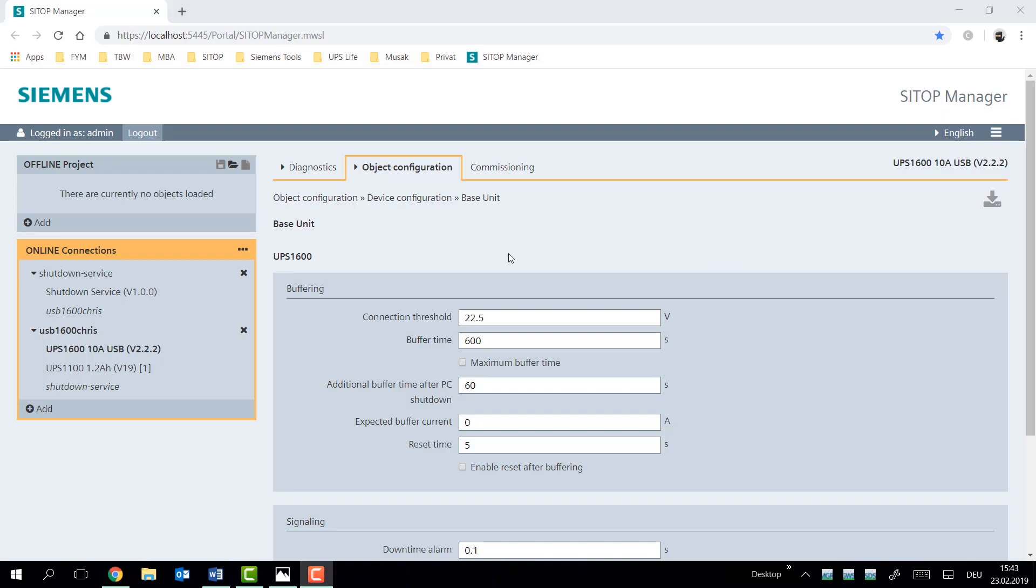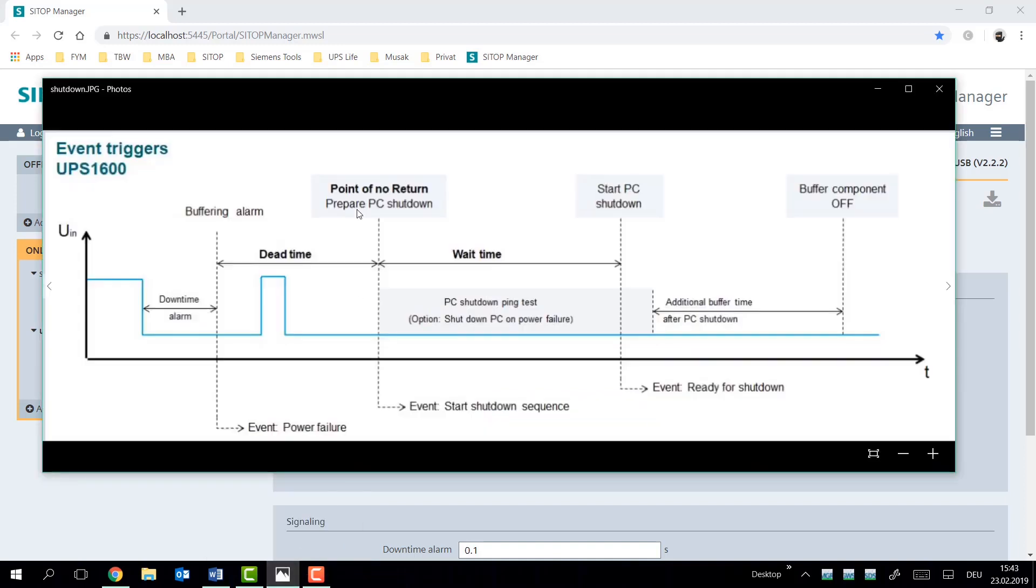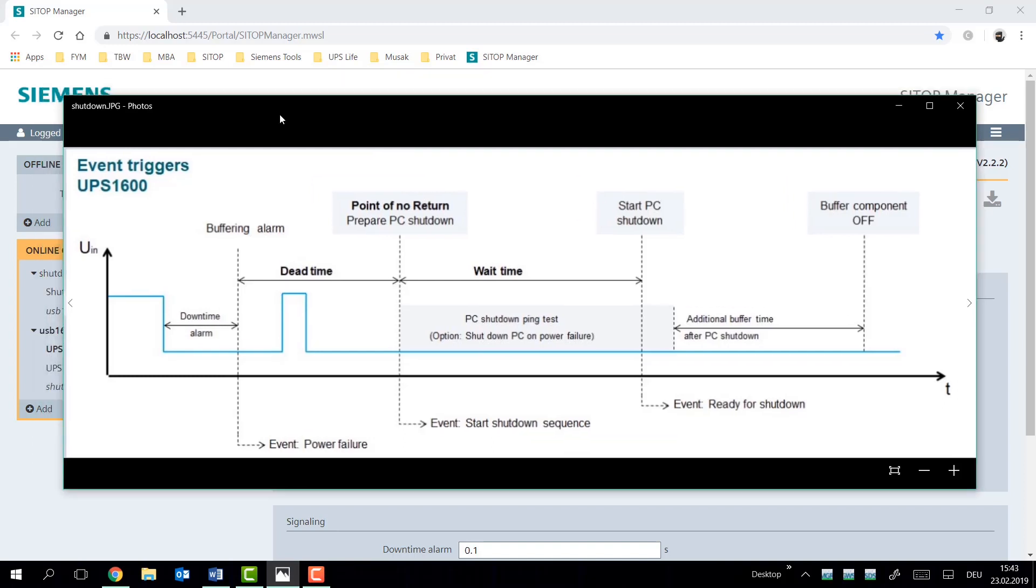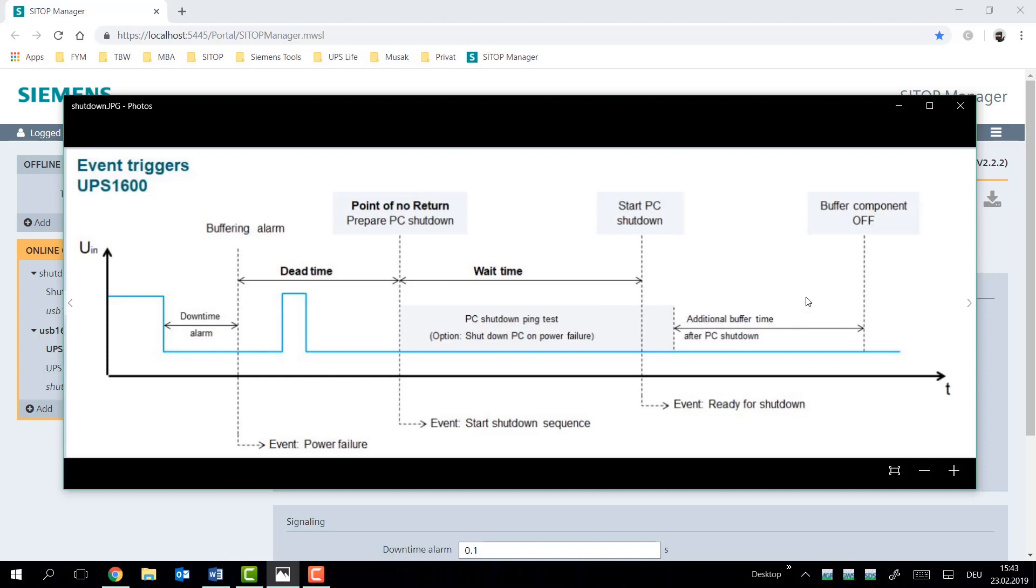The next parameter is the additional buffer time after PC shutdown. I'm going to pull up the diagram we use in the shutdown service, you'll see in another video, of how a shutdown is documented in the SITOP manager. What we see here is the additional buffer time after PC shutdown is on the right-hand side, and it refers to the time after the PC shutdown command has been given, and the PC ping test, the method in which we communicate with the PC, has been successfully ended, and the amount of time we wait before we shut off the output on the UPS.